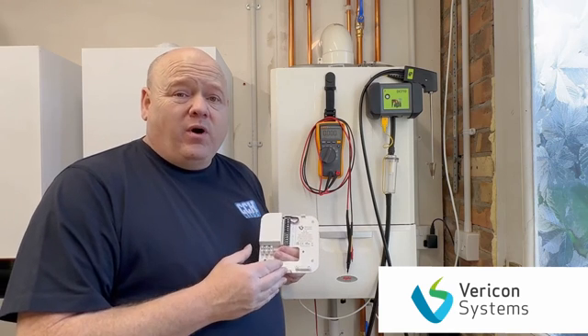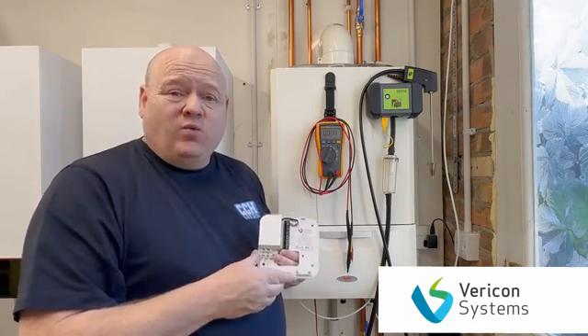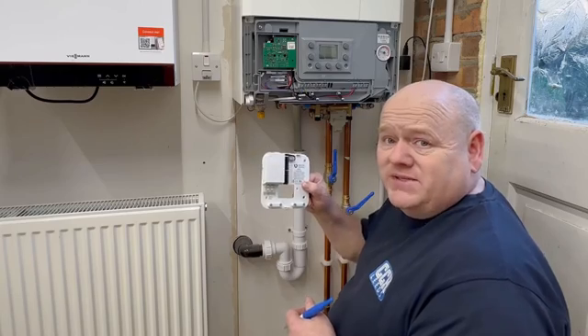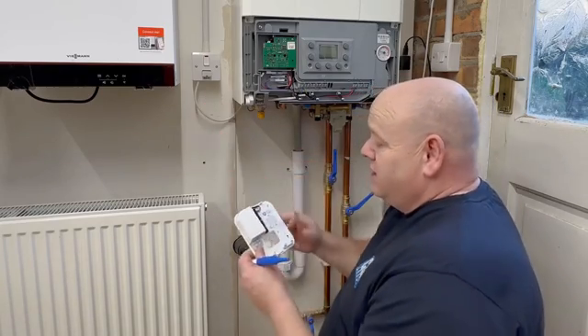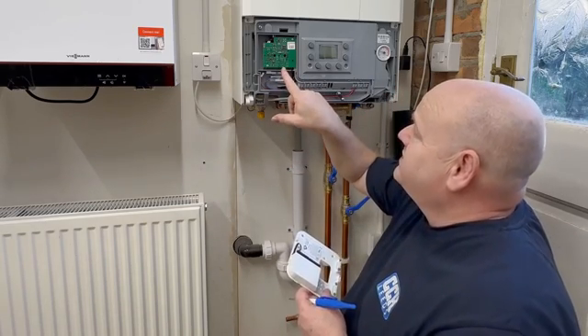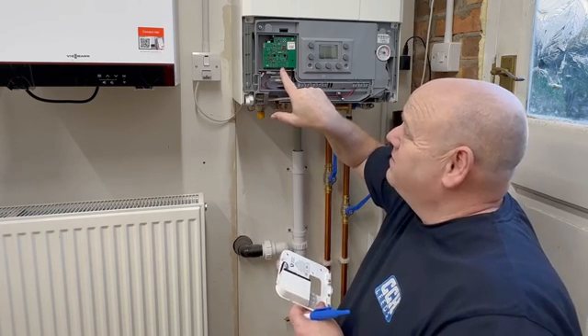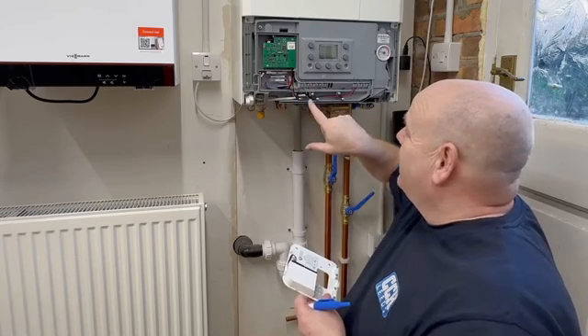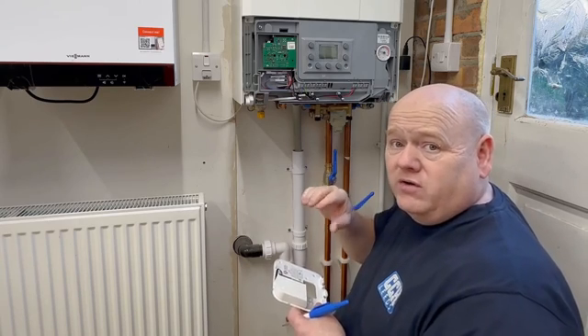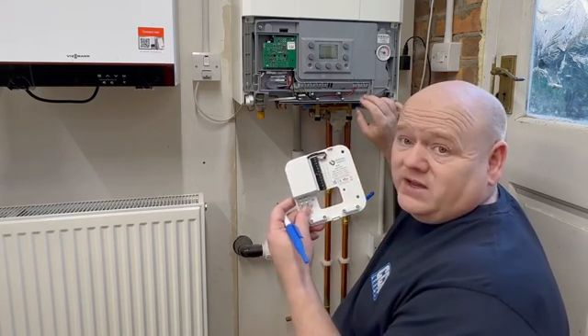I'll turn the power off to the boiler and make sure it's electrically safe, then remove the case and connect the wires. I'm going to mount the BCM on the wall — mark it, drill it and put it on. Looking at the wiring on this Alpha boiler, it's got the thermostat receiver built in. I'll remove the existing OpenTherm wires and connect them to the BCM, then bring wires back from the BCM and connect them into the boiler.